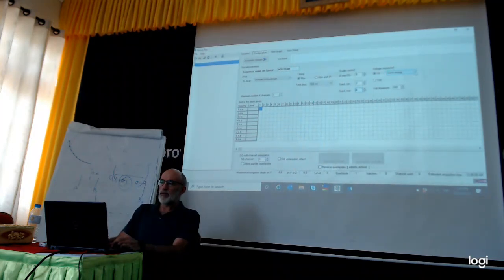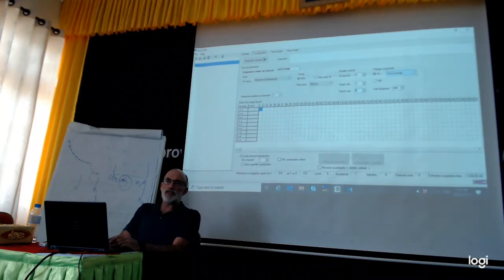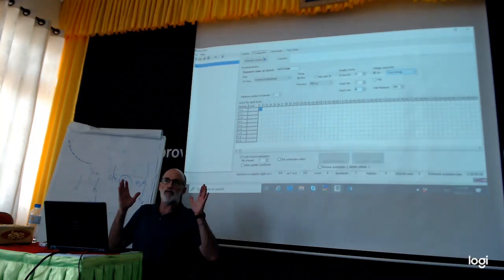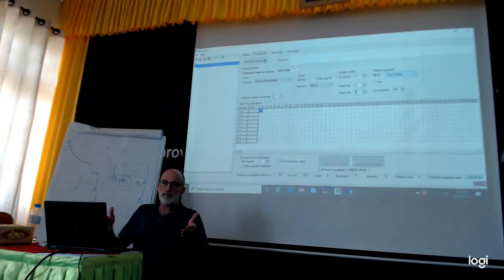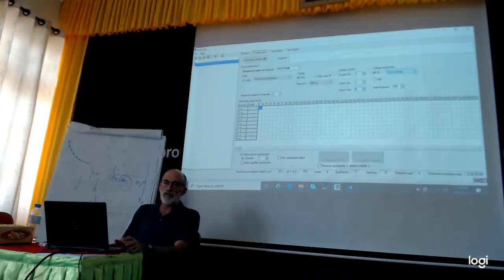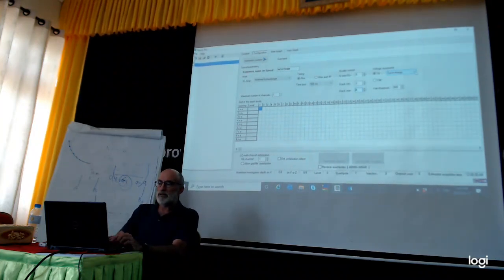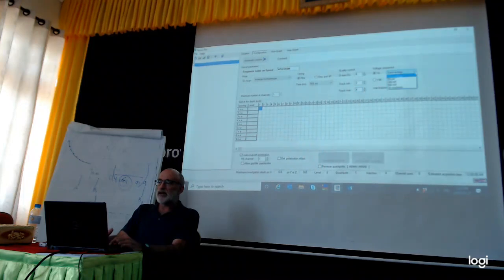And the save energy setting just puts in a minimum amount of current to get a potential voltage out. But we and Iris recommend using the 50 millivolt setting.